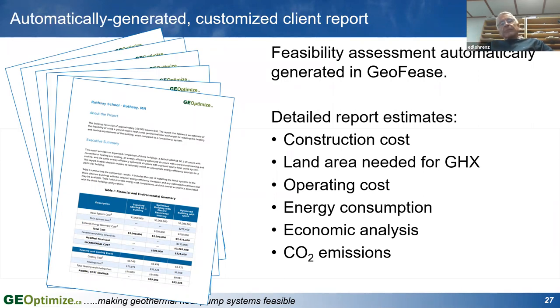It's not going to give you a number for your specific building, because the only way to do that properly is to build an energy model for your specific building, but it can give you a much better estimate than typical rules of thumb of 400 square feet per ton or 200 feet of drilling per ton. This can change it pretty significantly.